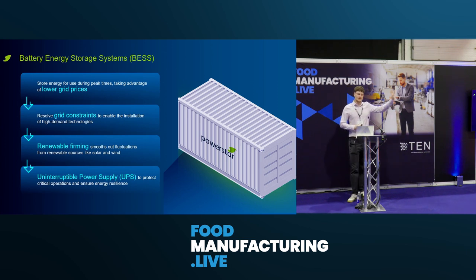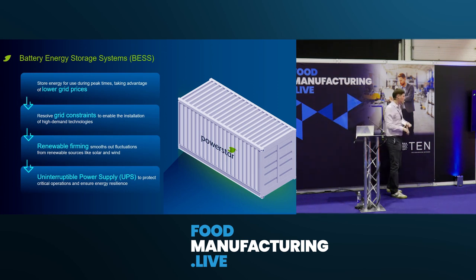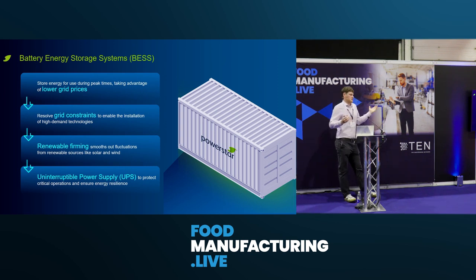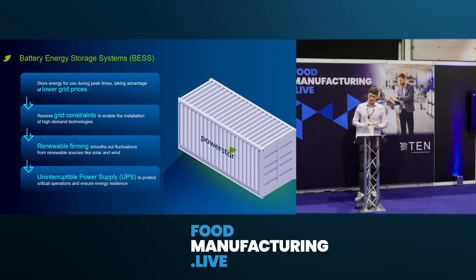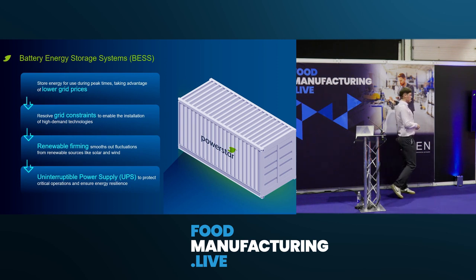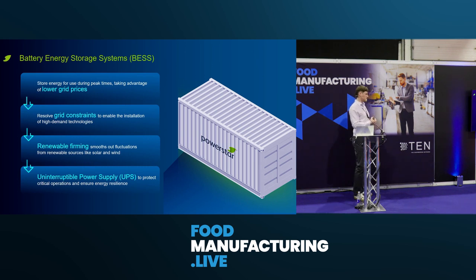Actually, this thing can do way more than just renewable firming. There's overcoming grid constraints, again using a battery to parallel feed the peak power when some of the drives or devices are running. Using a battery to boost that power supply for a number of hours while that machine is running or starting up is something the battery can do. So rather than paying National Grid or your local DNO an obscene amount of money to put a bigger cable in the road or upgrade the downstream supply point, putting a battery in allows you to access the technologies needed to enable your decarbonisation.